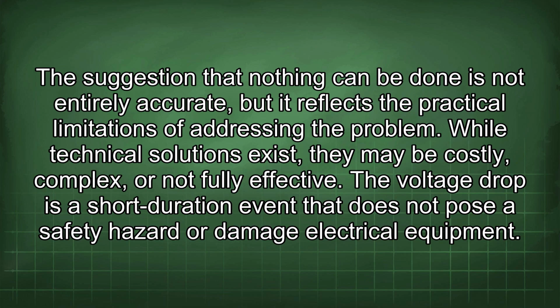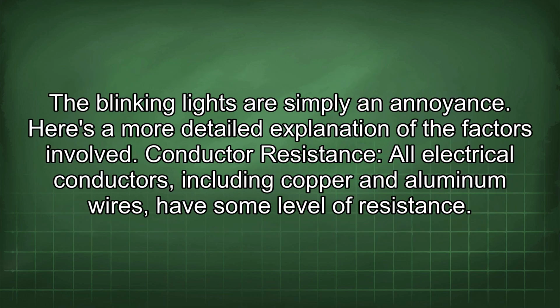The suggestion that nothing can be done is not entirely accurate, but it reflects the practical limitations of addressing the problem. While technical solutions exist, they may be costly, complex, or not fully effective. The voltage drop is a short-duration event that does not pose a safety hazard or damage electrical equipment. The blinking lights are simply an annoyance. Here's a more detailed explanation of the factors involved.